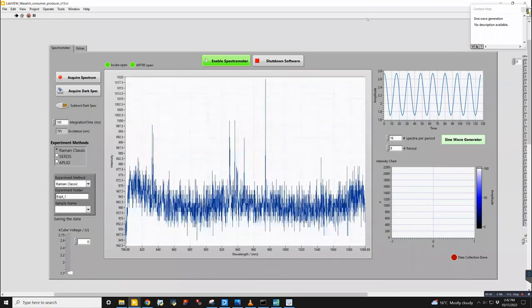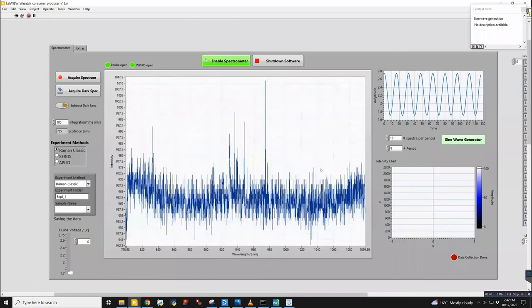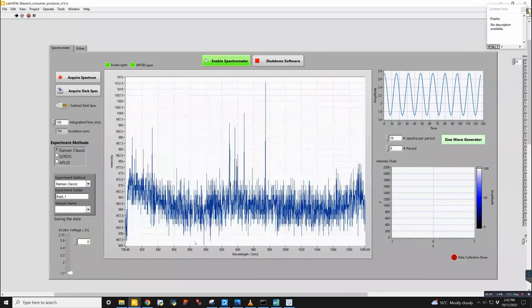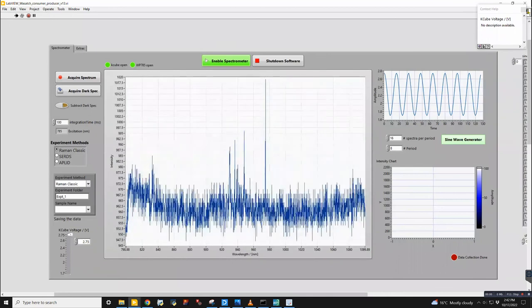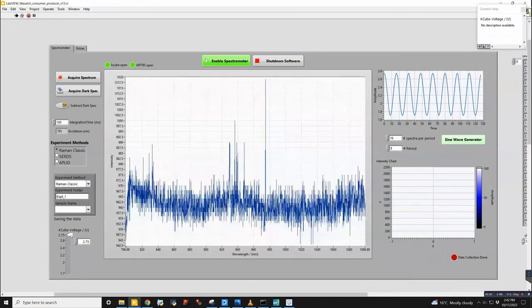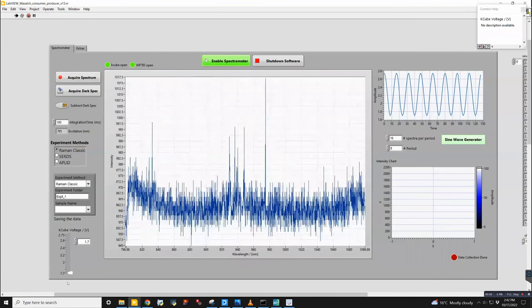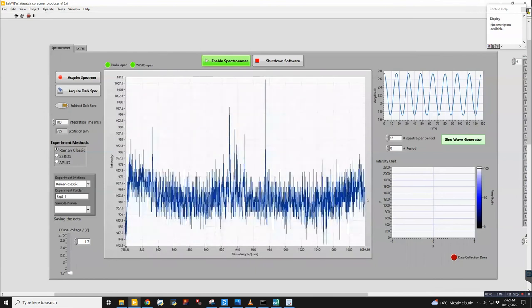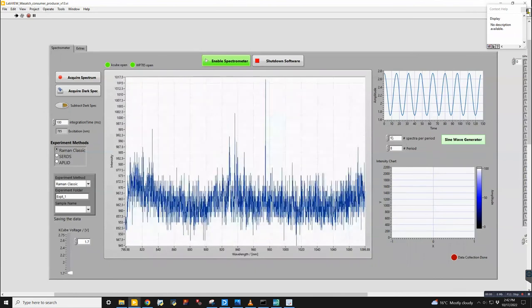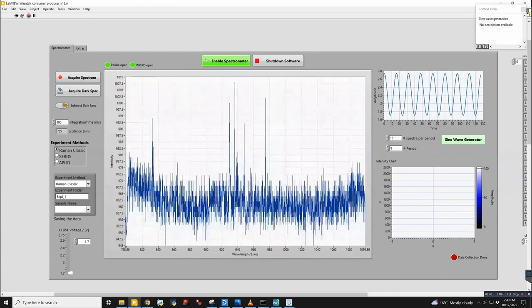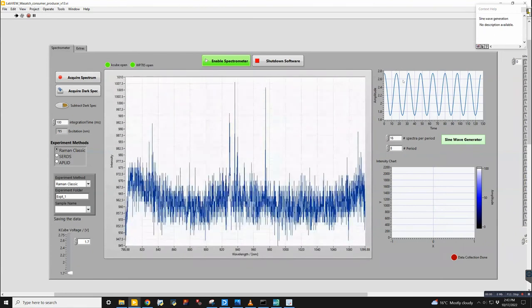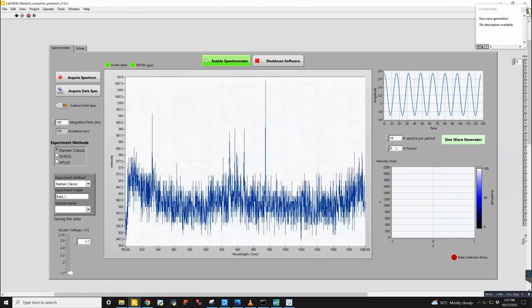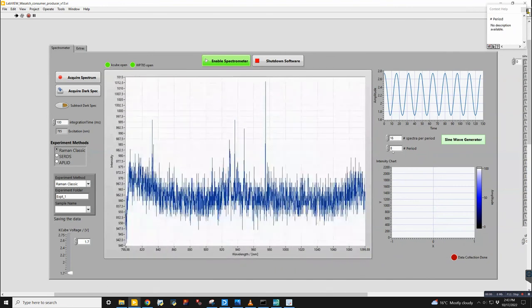modulating the voltage. So the minimum and maximum voltage is set by default over here. So 2.75 is the maximum voltage for one laser, and then 1.7 is for the other. It will modulate between those. We'll take 16 spectra per period. So the peak to peak number of data points is 16, and it repeats that 8 times. And that's pretty much it.